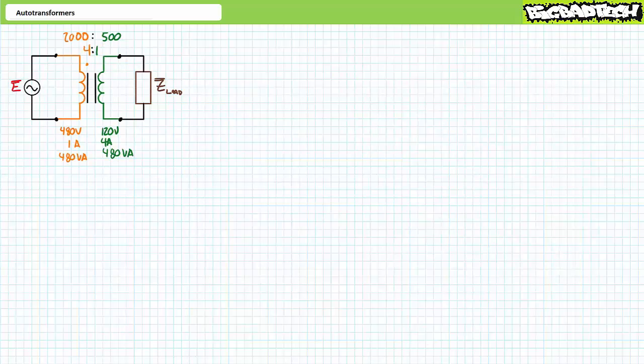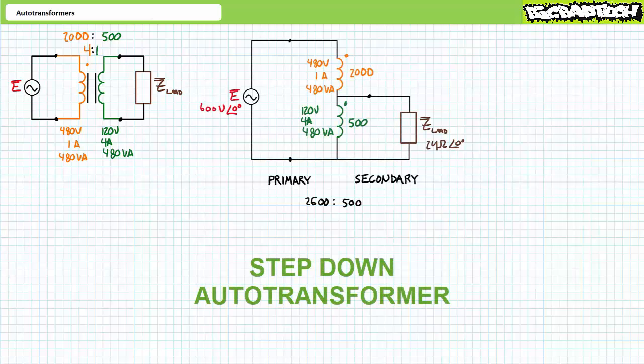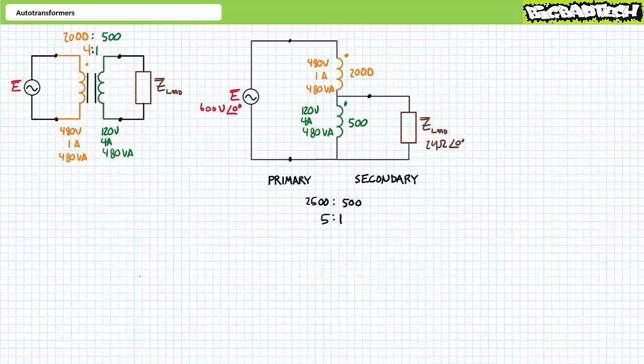As an example, consider a traditional four-to-one step-down transformer with a 480 volt one amp rated primary and a 120 volt four amp rated secondary for a total rating of 480 volt amperes — with a primary of 2000 turns and secondary of 500 turns. Now consider these same windings configured as a step-down auto transformer with 2000 plus 500 or 2500 turns in the primary and 500 turns in the secondary. This means 480 plus 120 or 600 volts can be applied to the primary. The turns ratio of 2500 to 500 makes this a five-to-one step-down auto transformer, stepping 600 volt input down to 120 volt output.